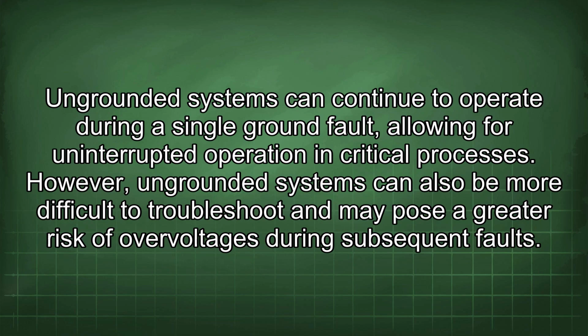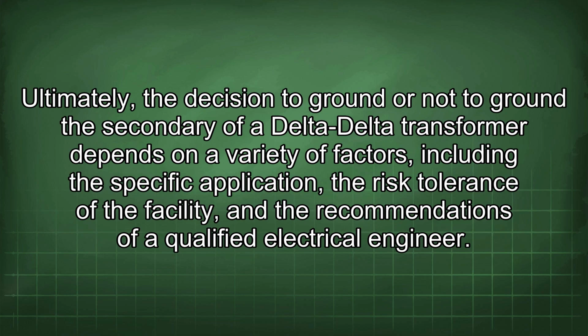Conversely, ungrounded systems can offer benefits in certain applications. Ungrounded systems can continue to operate during a single ground fault, allowing for uninterrupted operation in critical processes. However, ungrounded systems can also be more difficult to troubleshoot and may pose a greater risk of overvoltages during subsequent faults. Ultimately, the decision to ground or not to ground the secondary of a delta-delta transformer depends on a variety of factors, including the specific application, the risk tolerance of the facility, and the recommendations of a qualified electrical engineer.